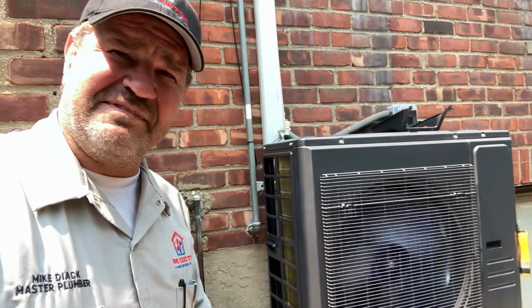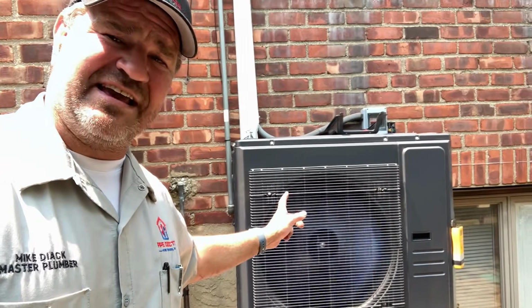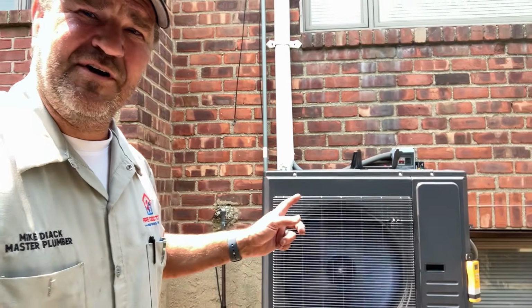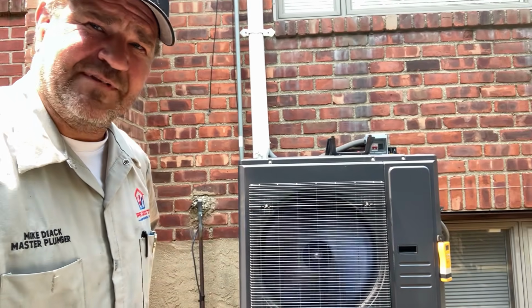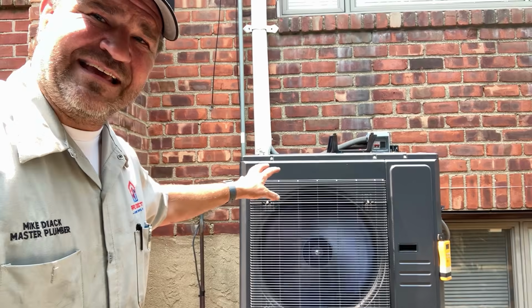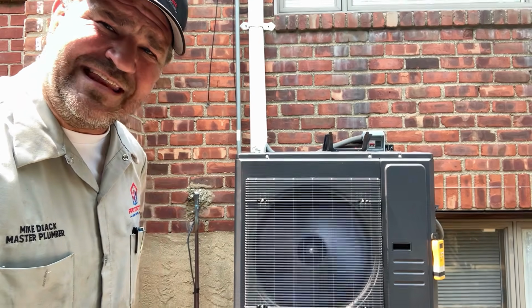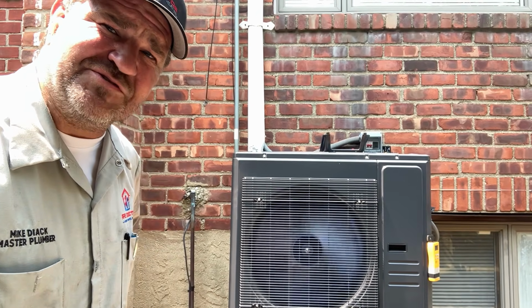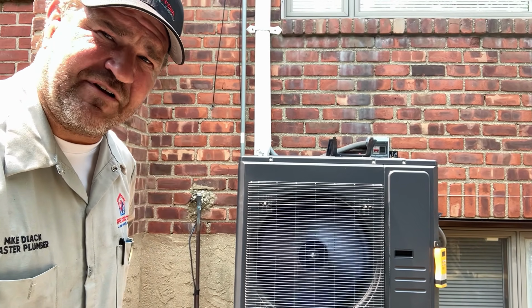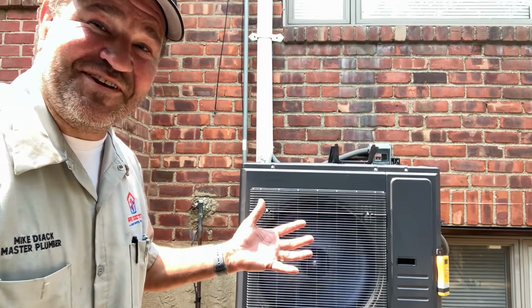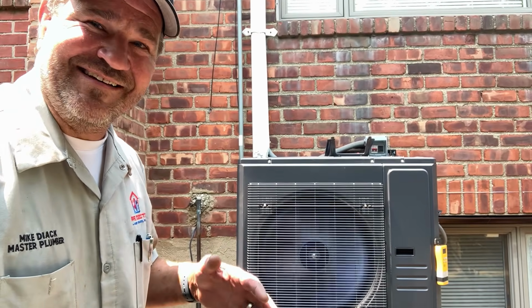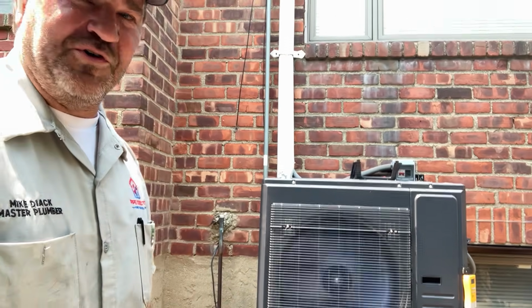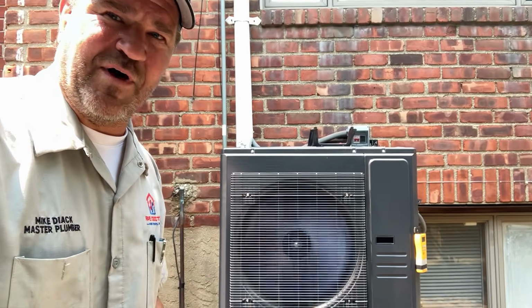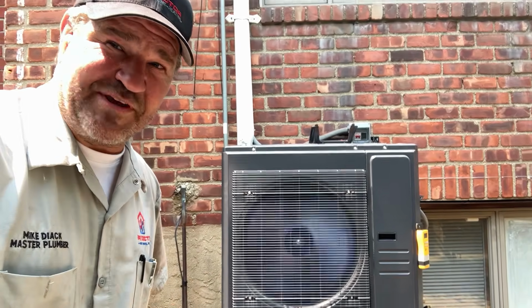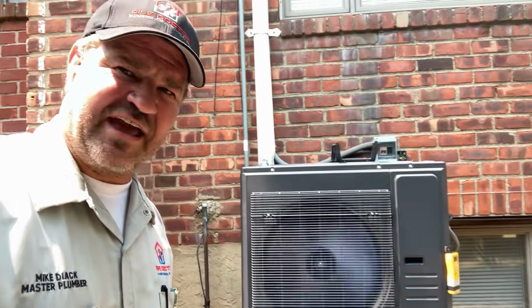And here's something that really separates this ACiQ Extreme Plus system from a lot of equipment on the market. This heat pump can deliver 100% heating capacity all the way down to minus 15 degrees Fahrenheit. Years ago, and people still think this now, right? Heat pumps don't work well in New York. They don't work well in cold climates. Well, that simply isn't true anymore. Modern inverter technology has completely changed the game.